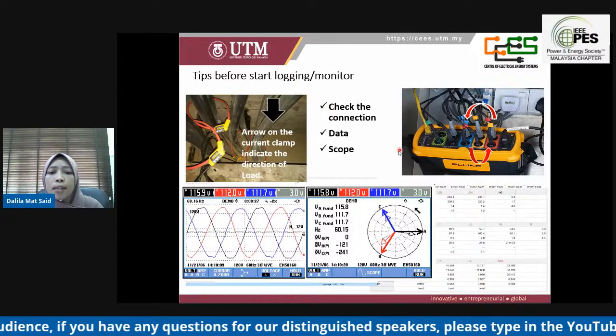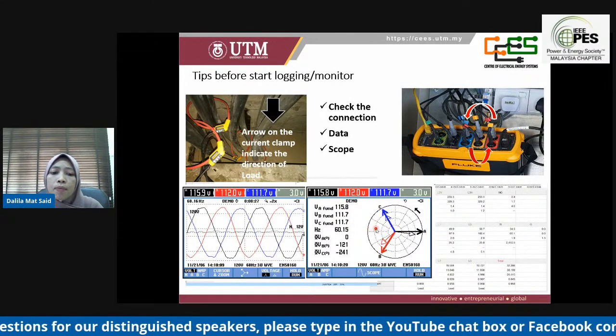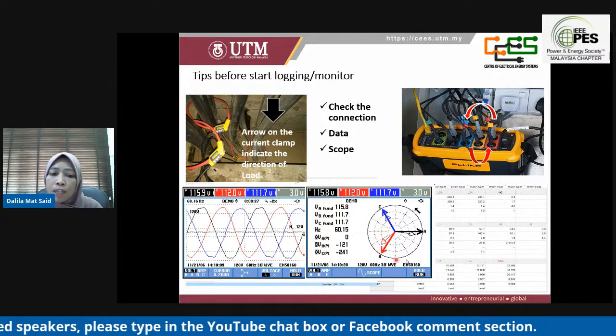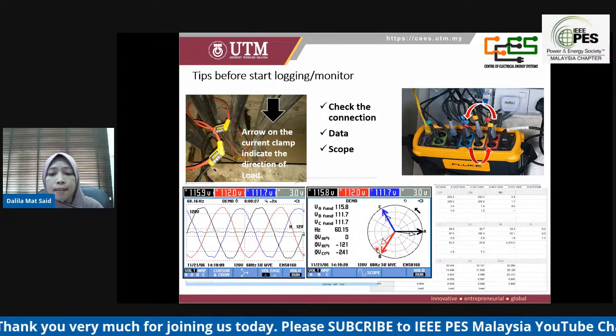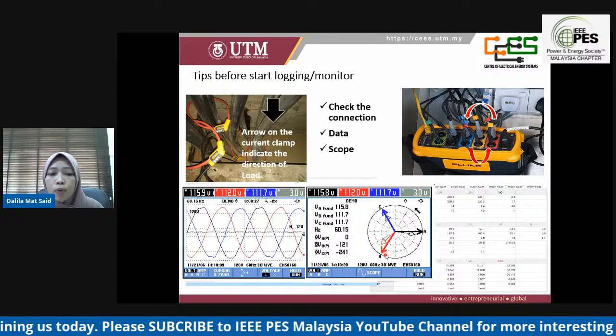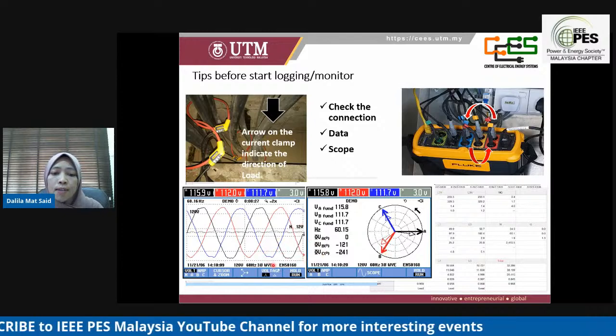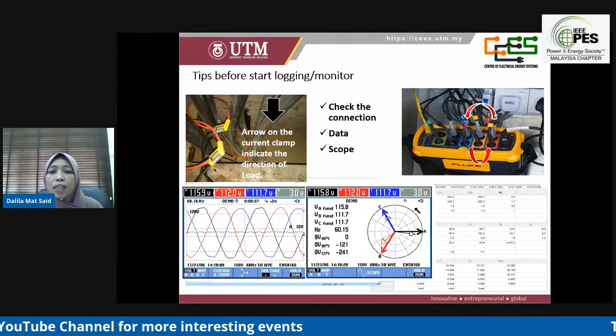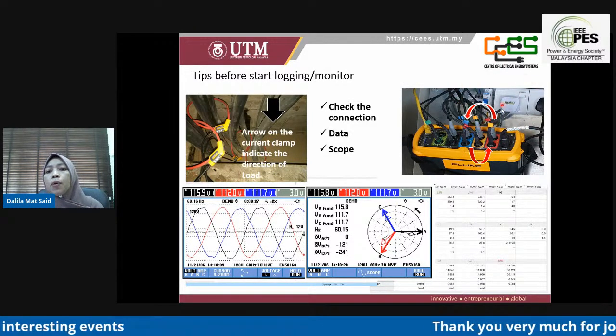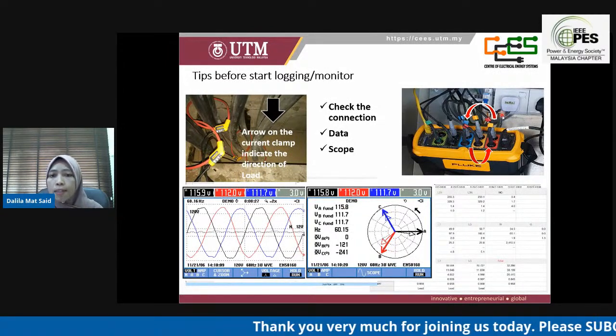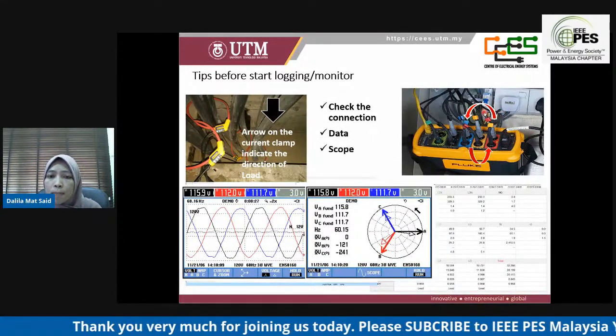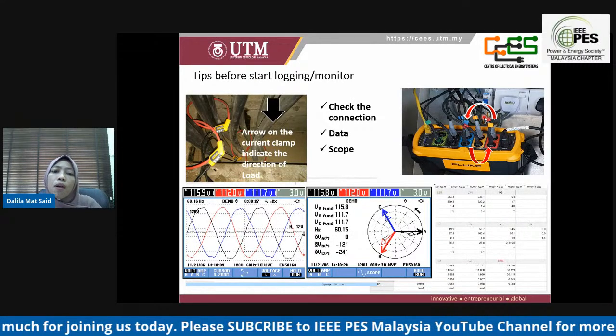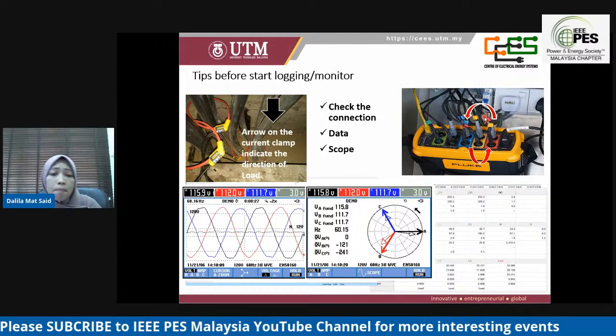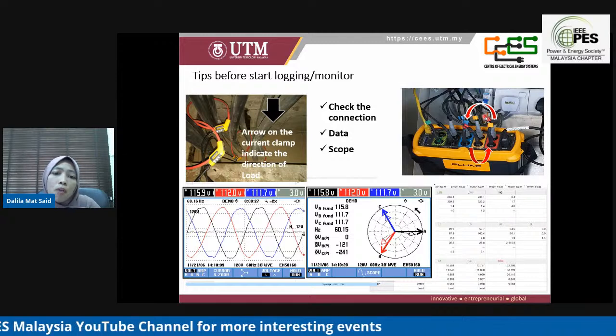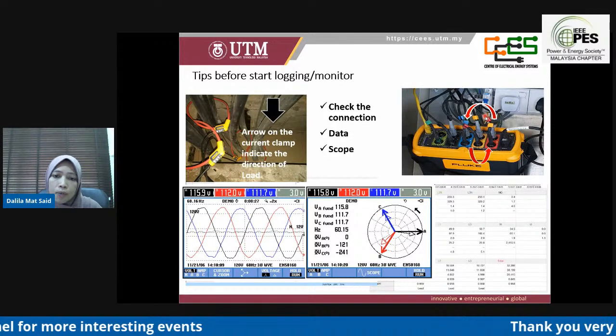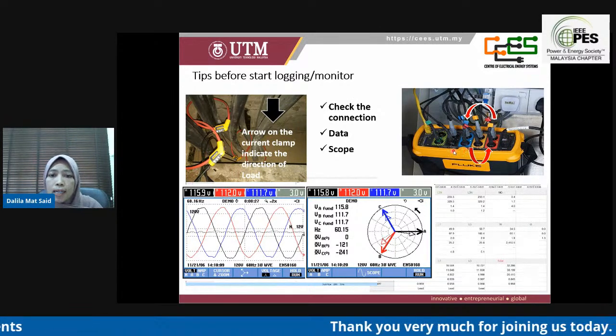And the second one is we can check the scope function, and if we have a three-phase system, we should see something like this, that all the three phases are out by about 120 degrees. And also we can check the reading on the meter. And another part, if you carefully observe this type of connection, you can see what the error is in this type of connection. And this is also an important part that we need to check before you leave your monitoring for about a week or a month or a year. But even if it is for a long duration, we need to check the data frequently. So these are some tips before we start logging and monitoring.